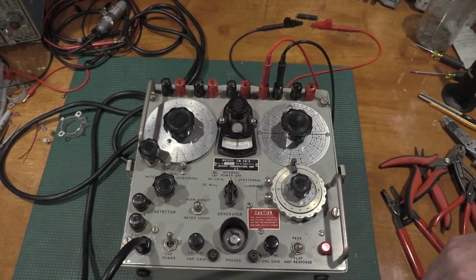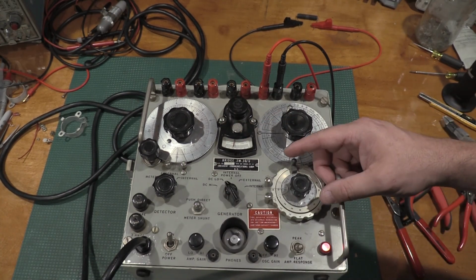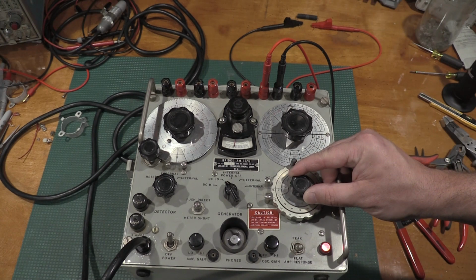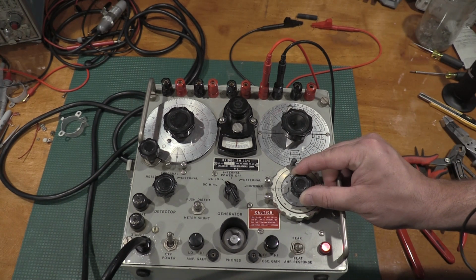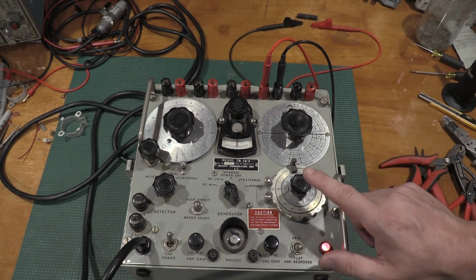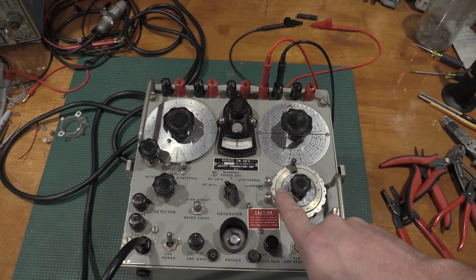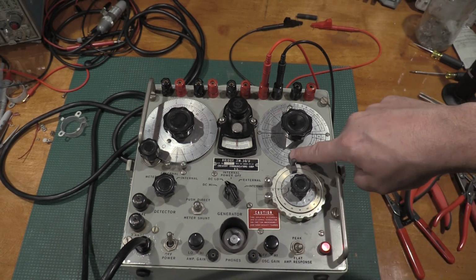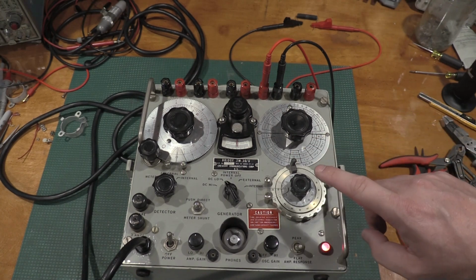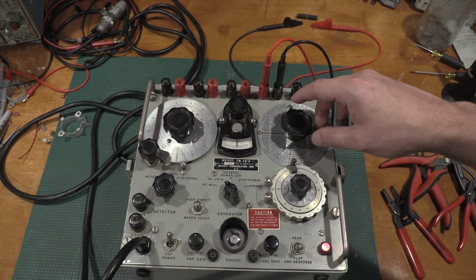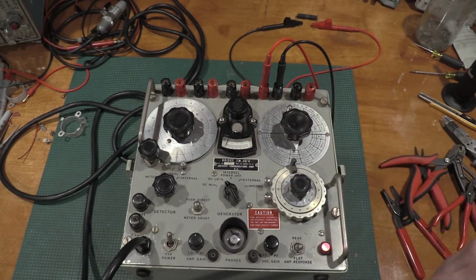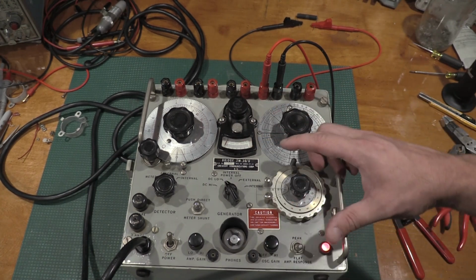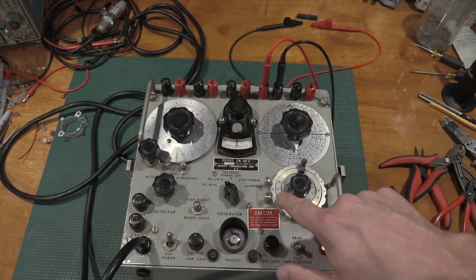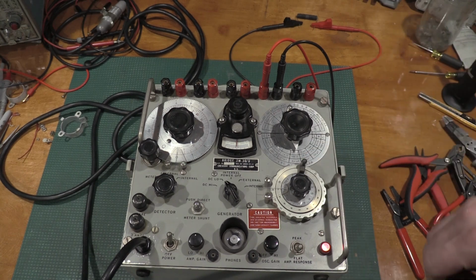So if I kick this over to 1K on the 1X range, and I say give me some DC, it's going to throw me off a little bit. But I can bring the meter back into alignment with the center dial. But this is 0.01 on the 1X, on the 1K range. That means 10 ohms. So if I bring this down a range, it's going to say my resistance setting is way too high. I need to bring that down. I'm on the inner 0.1 at 100 is 10 ohms.